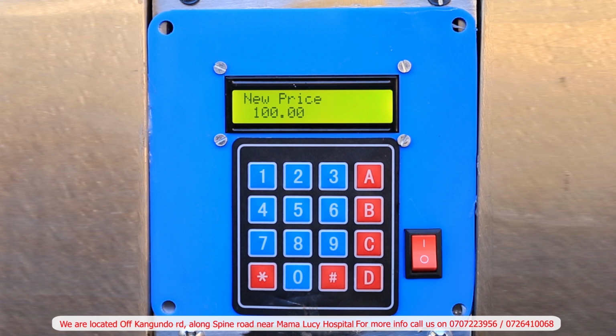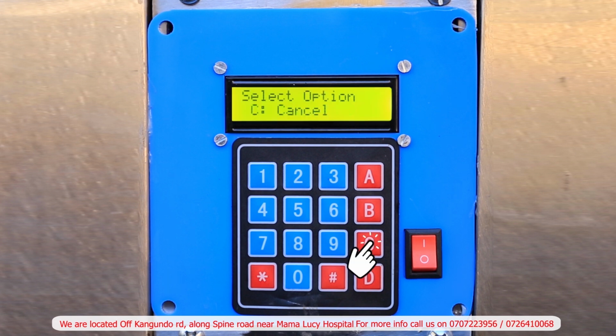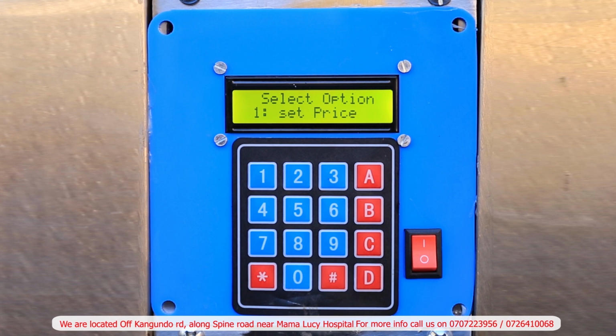It is recommended, every time you change the unit price of your product, to calibrate the ATM. Therefore, I will go back by pressing C, and scroll down by using the letter D to go to option 2, which is the calibration function. After displaying calibration function number 2, I will key in number 2, and then I will be required to key in the liters per minute that the machine is dispensing.